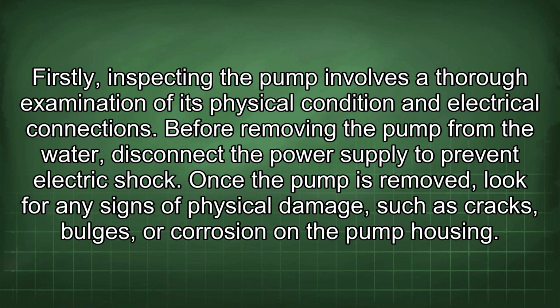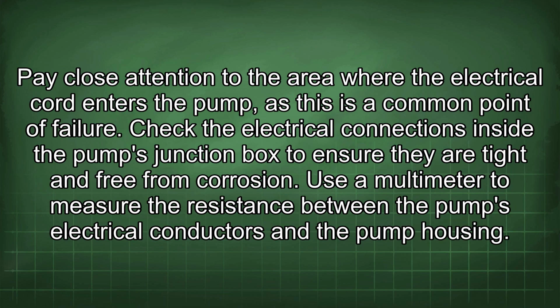Firstly, inspecting the pump involves a thorough examination of its physical condition and electrical connections. Before removing the pump from the water, disconnect the power supply to prevent electric shock. Once the pump is removed, look for any signs of physical damage, such as cracks, bulges, or corrosion on the pump housing.